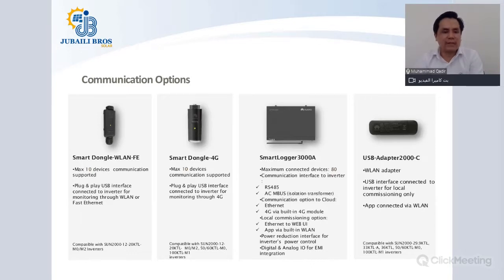For communication devices, we have WLAN-FE. These can be used for up to 10 inverters. This is a plug-and-play USB interface device, which is compatible from 3 kilowatt 3-phase to 20 kilowatt 3-phase inverters. The Smart Dongle 4G is kind of a similar plug-and-play device, which you can use up to 10 inverters for remote monitoring. And this is compatible from 3 to 20 kilowatt inverters, and also with the 50, 60, and 100 kilowatt inverters, this can be used.